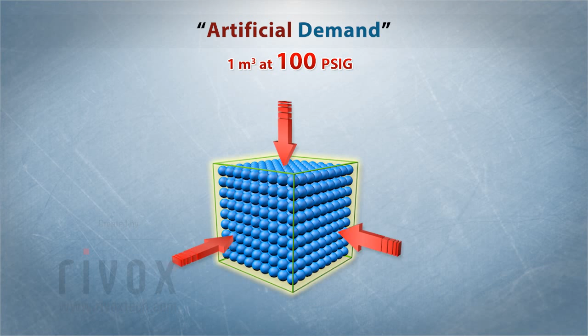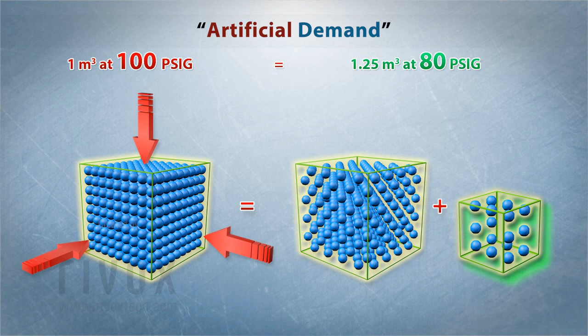Let's understand the effect of artificial demand. Consider 1 m3 of compressed air at a pressure of 100 psig. When this air is expanded from 100 psig to 80 psig pressure, it will occupy 1.25 m3 volume. Thus, for an application which requires compressed air of 1 m3 at 80 psig, when we supply 1 m3 at 100 psig, we end up supplying 0.25 m3 of air more, which results in artificial demand. This artificial demand increases with increased air pressure.